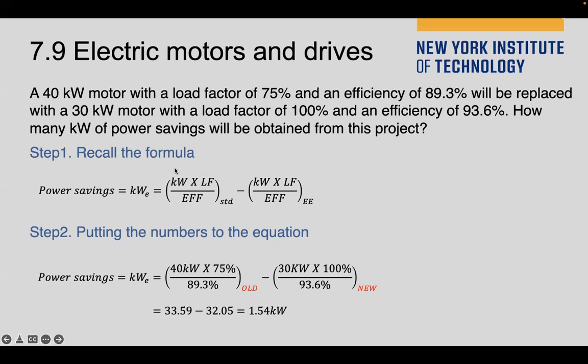Actually, for this equation, it's the power input to the motor. And this kilowatt is a nameplate kilowatt. So all the time, nameplate is the power printed or engraved on the housing of the motor. And for this, you can take a look on this page, and it explains to you what the load factor is, but of course the efficiency, I'm pretty sure you know about it.